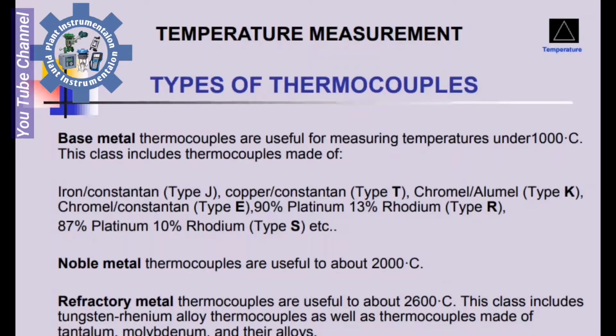Noble metal thermocouples are useful to about 2000 degrees Celsius. Refractory metal thermocouples are useful to about 2600 degrees Celsius. This class includes tungsten-rhenium alloy thermocouples, and thermocouples made of tantalum, molybdenum and their alloys.